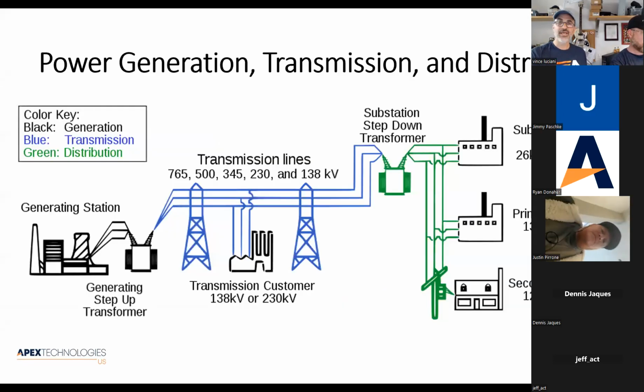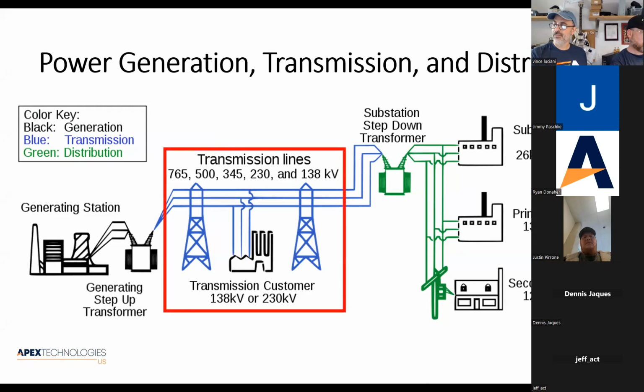So getting back to the main map here, that center section that you see in blue is the transmission side. On the generator side, I didn't even talk very much about the voltage at the generator. That's really not important, because right out of the generating station, they go directly into a step-up transformer that cranks the voltage way up to, as you can see here, anywhere from 138 to over 700,000 volts. The reason they crank it up so high is because power is voltage times current. So for a given amount of power that the generating plant generates, if the voltage goes way up, the current goes way down. And when you put less current through a wire, you minimize losses.